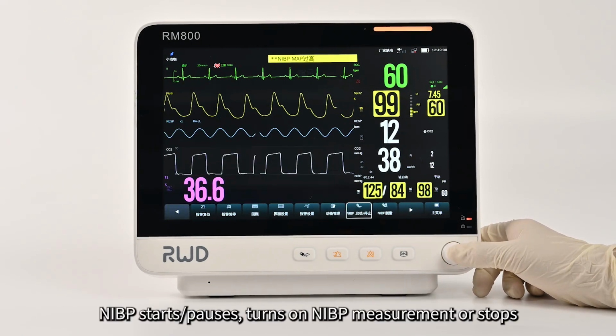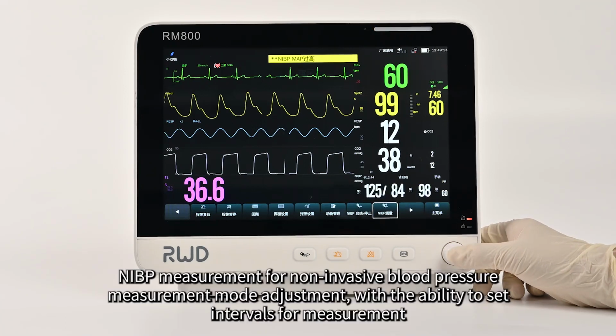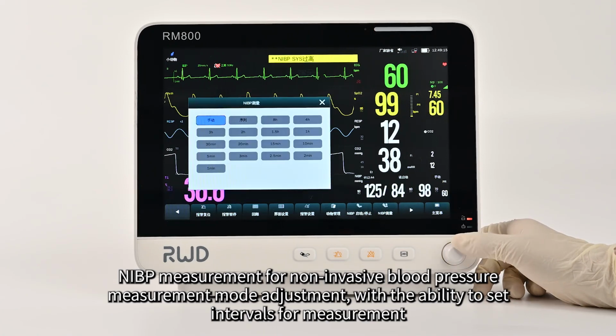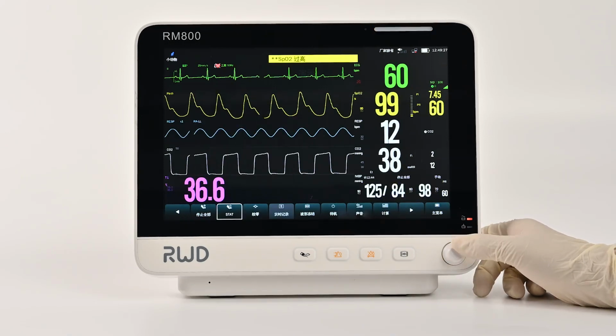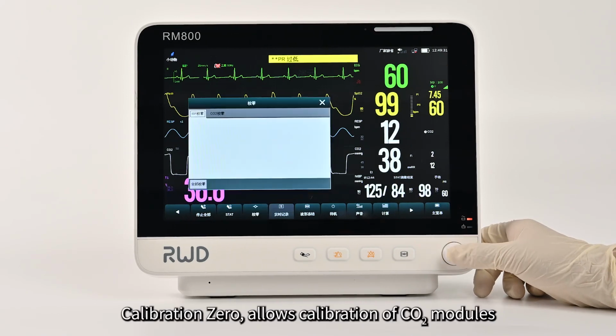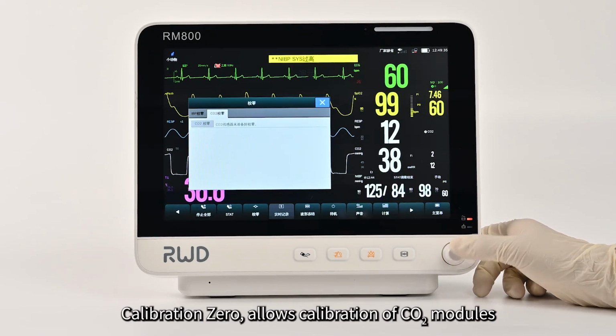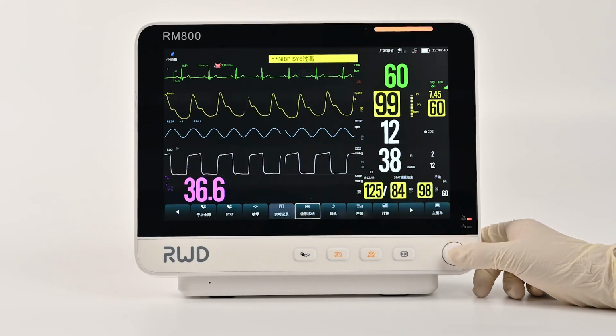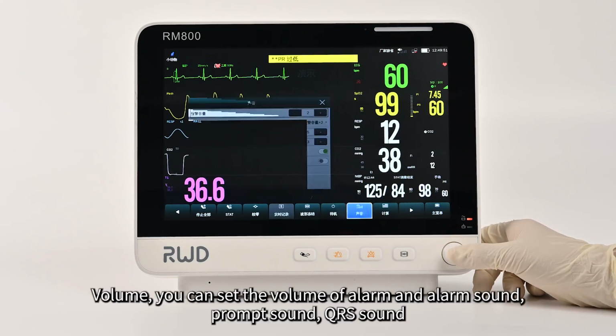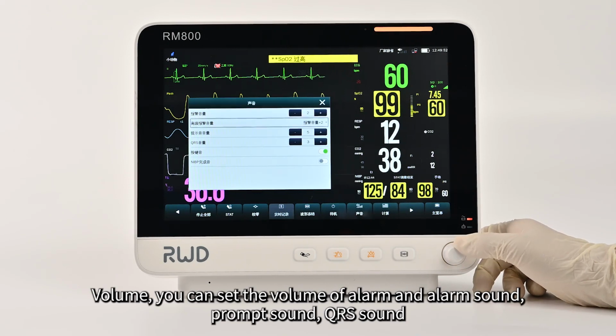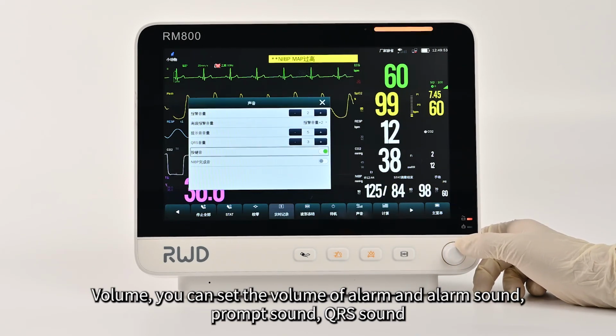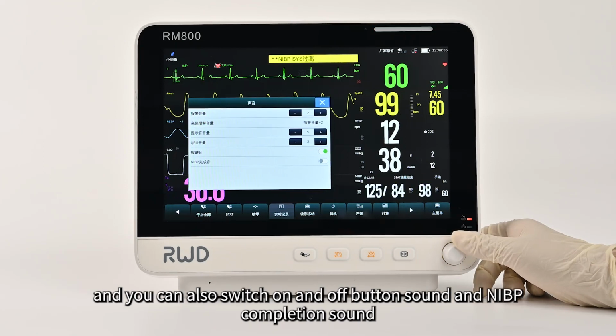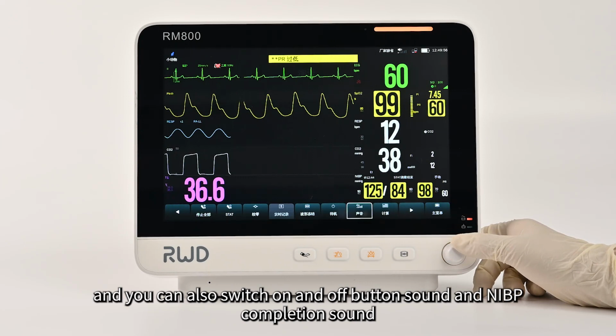NIBP start, pause, turns on NIBP measurement or stops. NIBP measurement is for non-invasive blood pressure measurement mode adjustment, with the ability to set intervals for measurement. Calibration 0 allows calibration of carbon dioxide modules. Volume. You can set the volume of alarm and alarm sound, prompt sound, QRS sound, and you can also switch on and off button sound and NIBP completion sound.